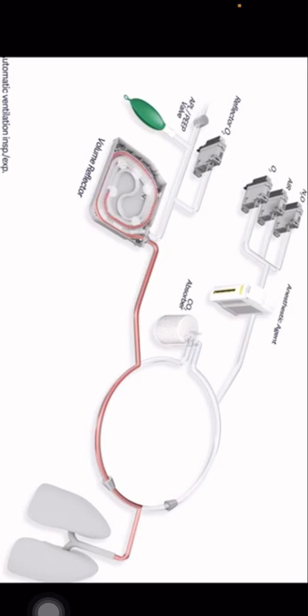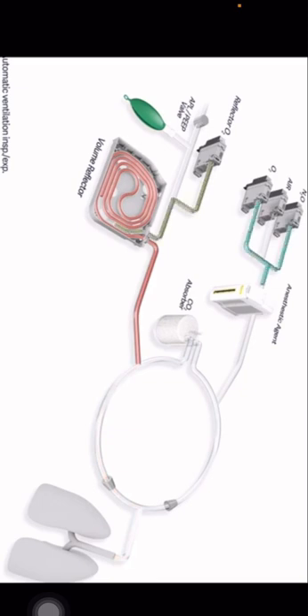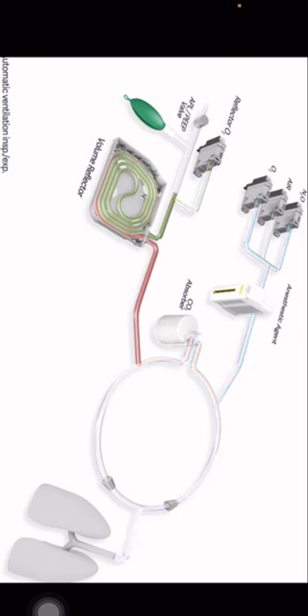It looks like a circle system in the anesthesia machine. A circle system improves the efficiency of anesthetic gas delivery to the patient by recycling gases expired from the patient, thus reducing the amount of fresh gas required. The fresh gas flow leaves the anesthetic machine, passes to the patient via a one-way valve during inspiration, and exhaled gases from the patient pass via a one-way valve into a reservoir bag or ventilator. Expired gas flow is delivered through the soda lime, which absorbs carbon dioxide. The APL valve allows excess gases to be removed from the system and reduces the risk of barotrauma.